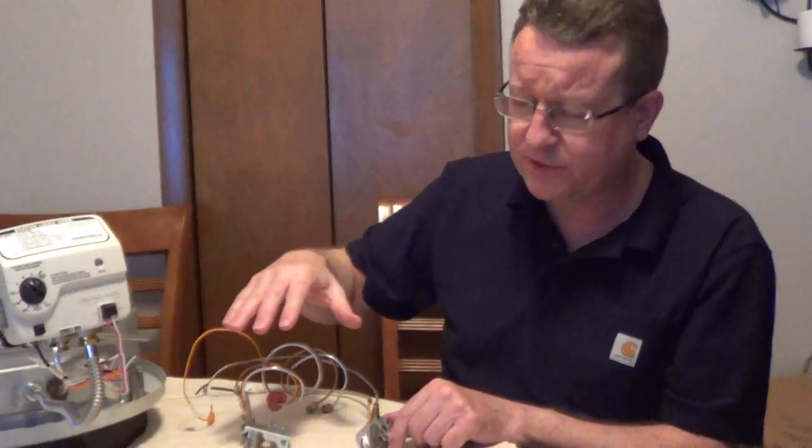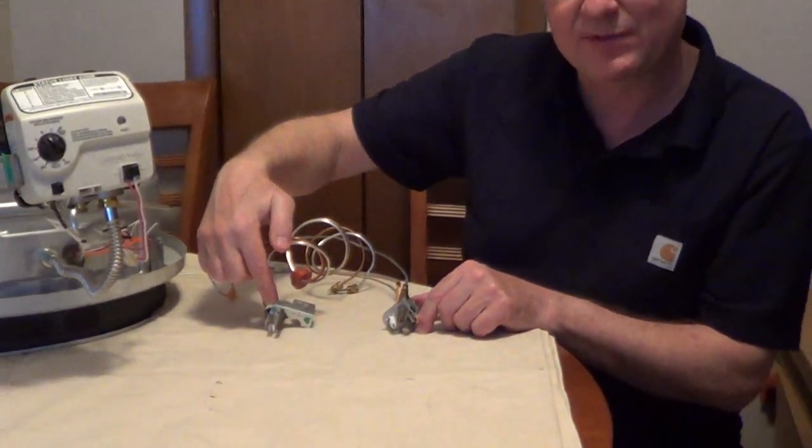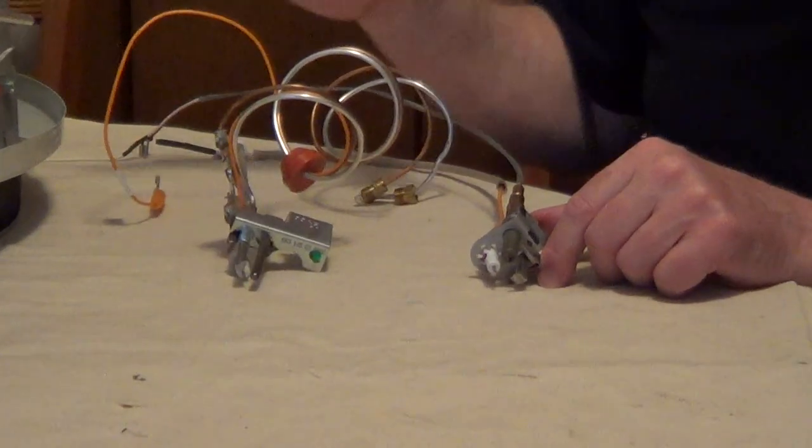I've had a question from homeowners on the difference between a thermocouple and a thermopile for a water heater. Before 2010, almost every manufacturer used a thermocouple to operate the gas control. This was your safety and generated about 75 millivolts.